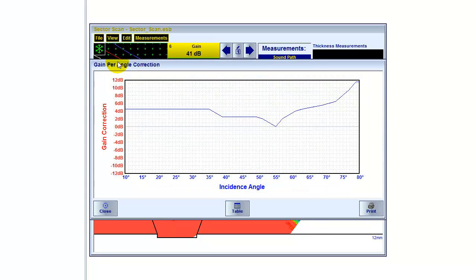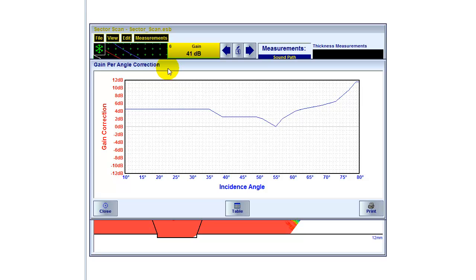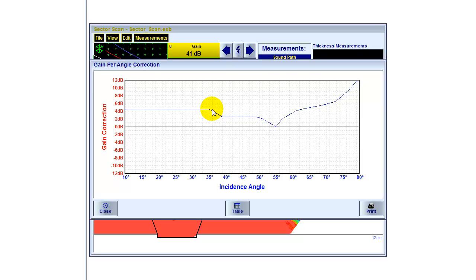There's another function which is called gain per angle correction. Now this is something important to understand. For every particular beam of the sector scan, we of course have a different incidence angle. And this incidence angle also refers to a different delay line in the wedge. That means depending on the length of this delay line, depending on the incidence angle, we have a different loss of energy, of sound energy. And there has to be a compensation for that in order to be more accurate.